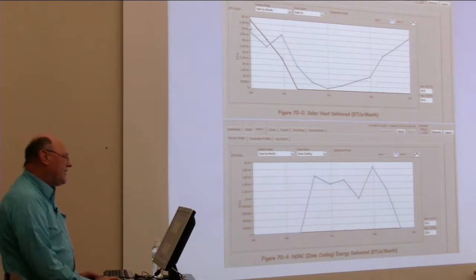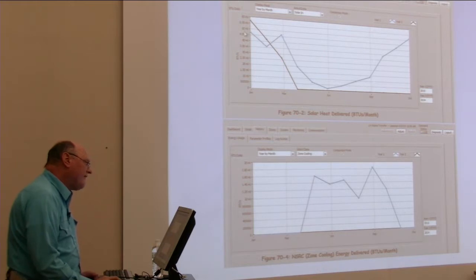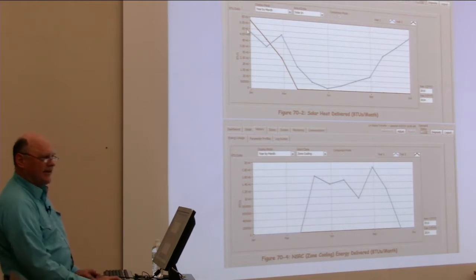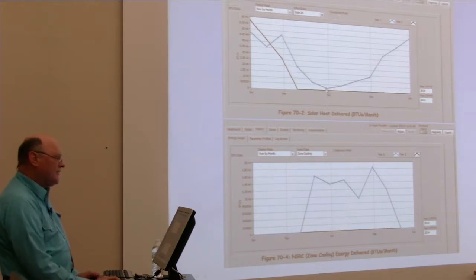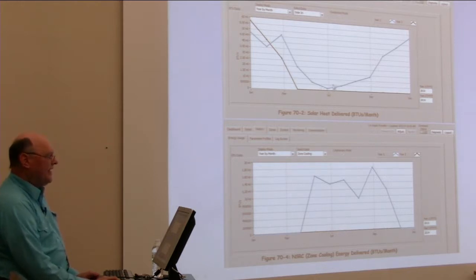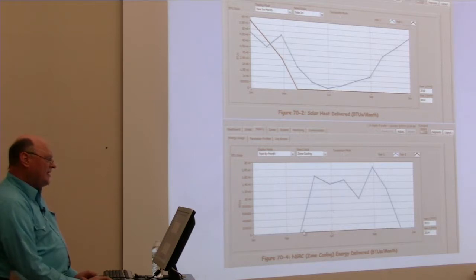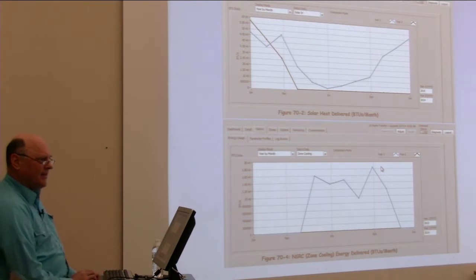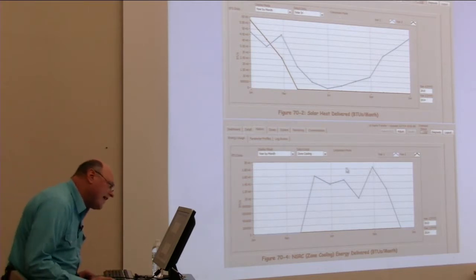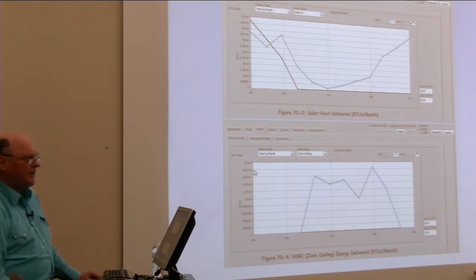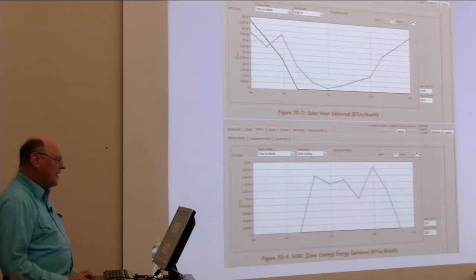So it was on the order, in the winter, of 5 million BTUs per month of solar heat delivered to the building. And in the summer, of course, it pretty much shut down except for the heat we needed to heat the domestic hot water tanks. But also, the same year, we monitored how much cooling came out of those big black radiators on the roof. And here it is in BTUs, month by month during the hot season. We actually measured the cooling coming from those panels. And the highest value here is up around 2 million BTUs per month of cooling delivered to the building. So not only are we using pretty unconventional means to do heating and cooling, we're measuring it and we're proving that it's working.